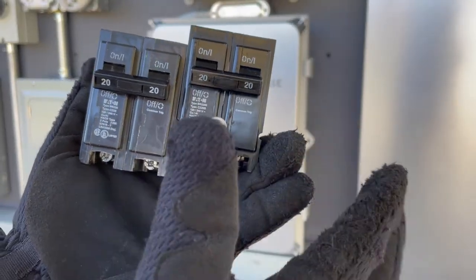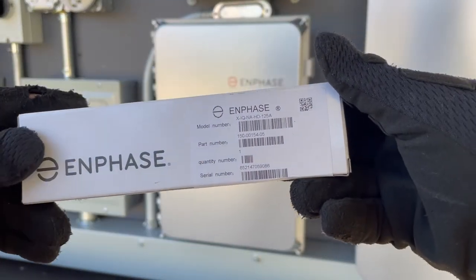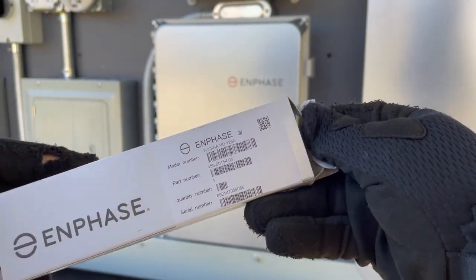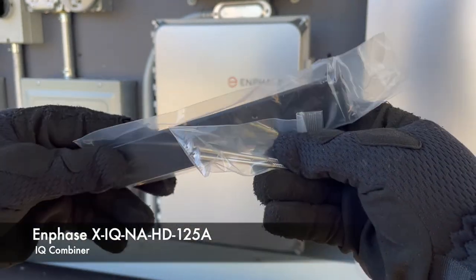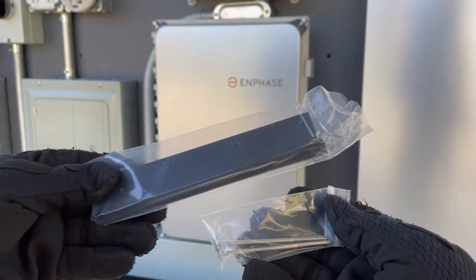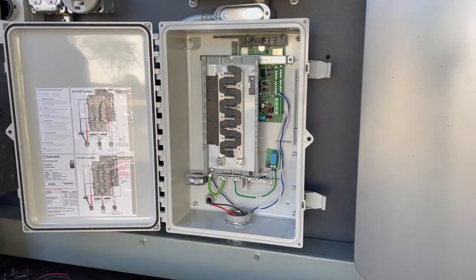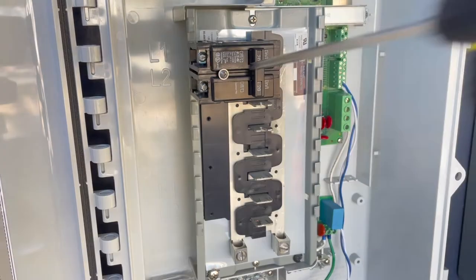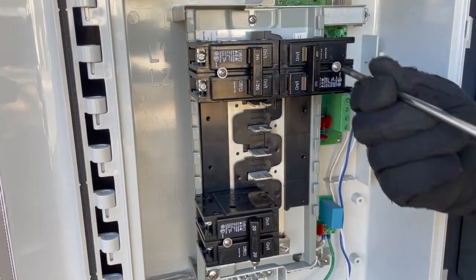Breakers that are 60 amps or greater always include this hole. Enphase makes a hold-down kit for the IQ Combiner 4; its part number is X-IQ-NA-HD-125A. They are available at your Enphase distributor and the Enphase store online. Each of these kits includes a retaining clip and two screws. One kit will support two hold-down compatible breakers on one side; a kit is installed on the left and another is needed on the right side — two kits per combiner.